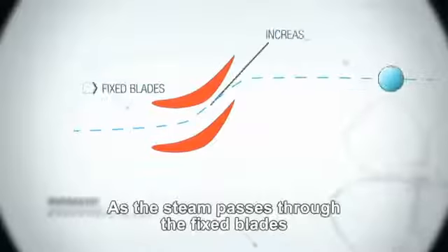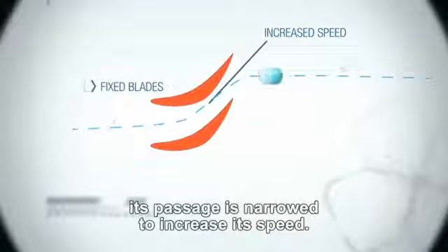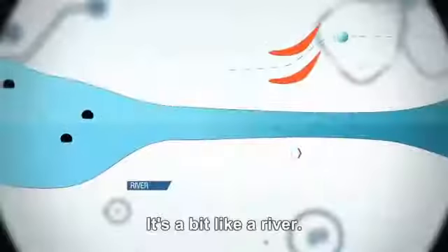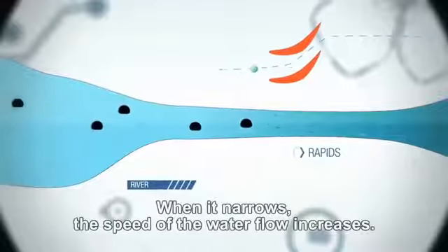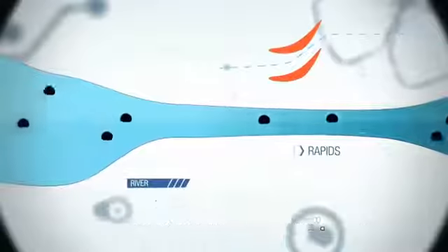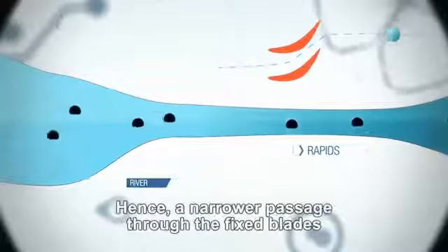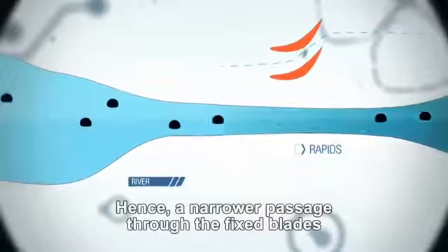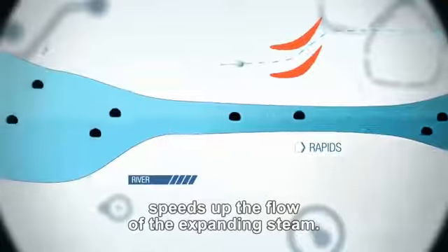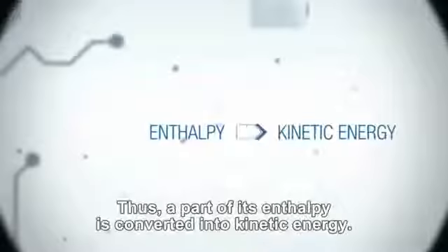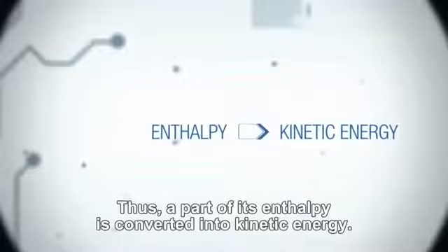As the steam passes through the fixed blades, its passage is narrowed to increase its speed. It's a bit like a river. When it narrows, the speed of the water flow increases. It's what we call rapids. Hence, a narrower passage through the fixed blades speeds up the flow of the expanding steam. Thus, a part of its enthalpy is converted into kinetic energy.